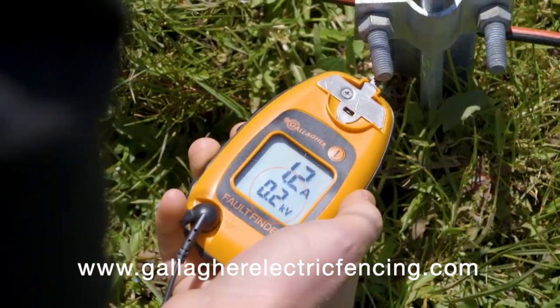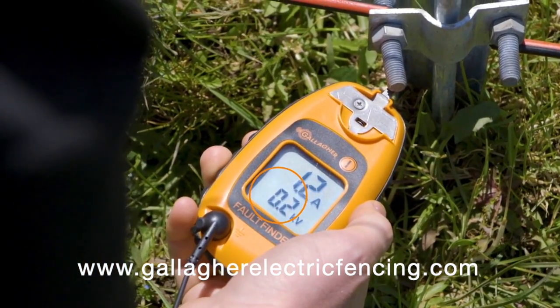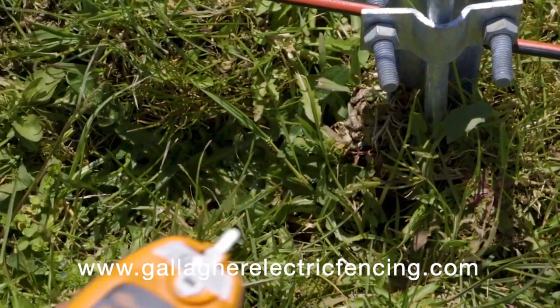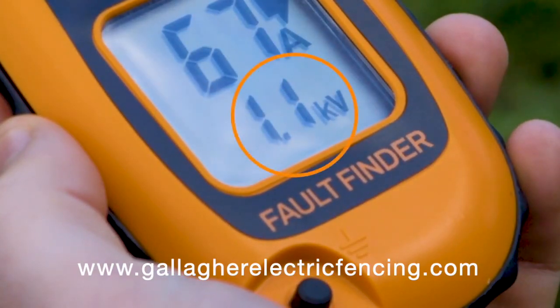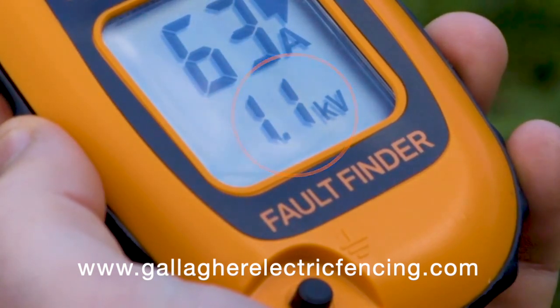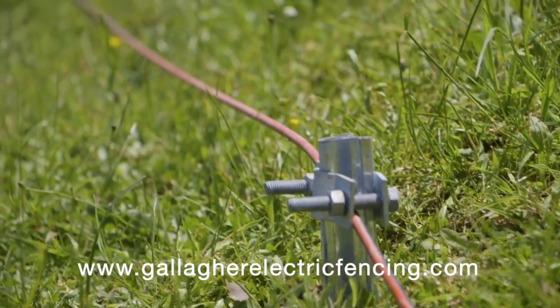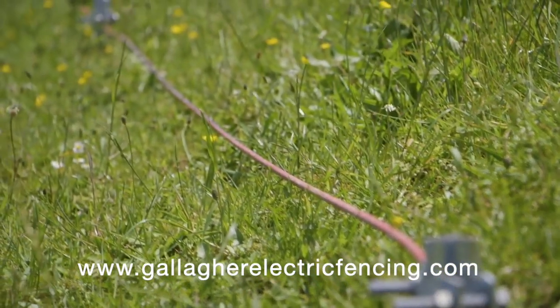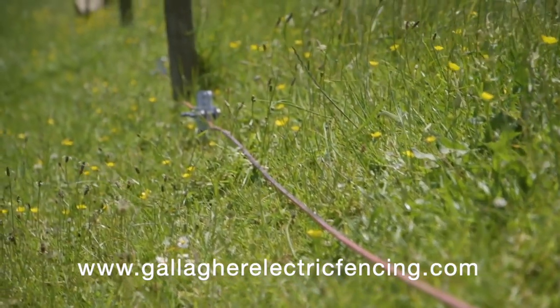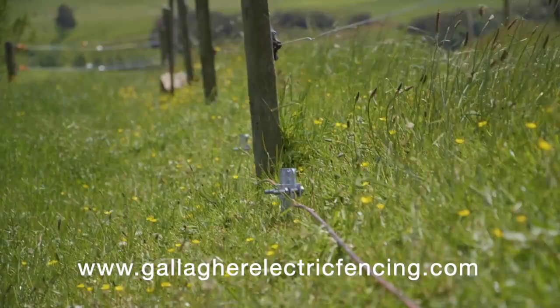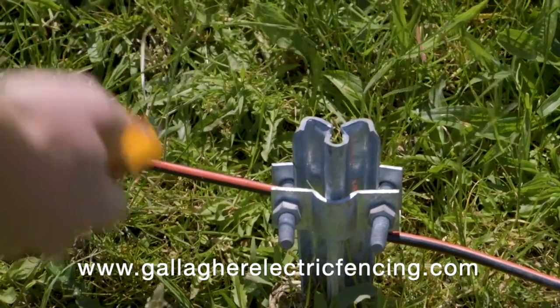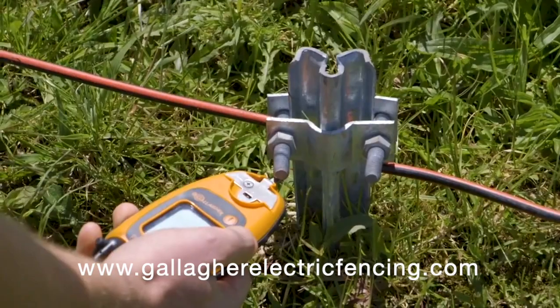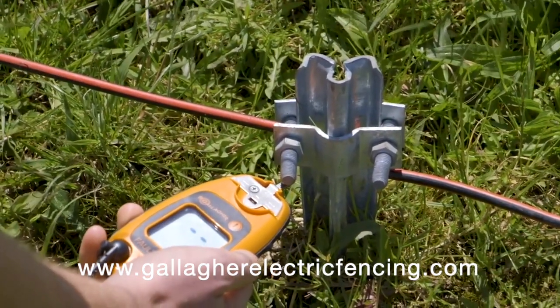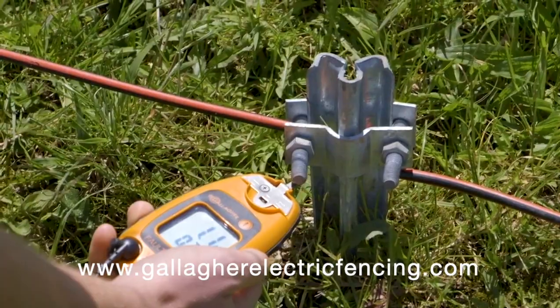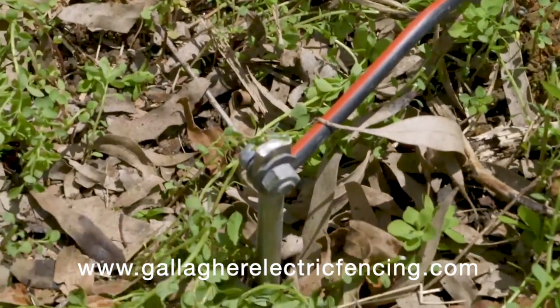If the reading is below 0.3 kilovolts, then the earth is working with the current load on the fence. If the reading is greater than 0.3 kilovolts, then there is a problem with the earth. To rectify the earth fault, you'll need to improve the quality of your earth. This can be done by firstly fixing any joint or cabling issues. If that does not resolve the problem, then you can put the earth or ground stakes into more conductive soils or add more earth or ground stakes. If you're still having trouble establishing an effective earth, then Gallagher recommends you consider using super earth kits.